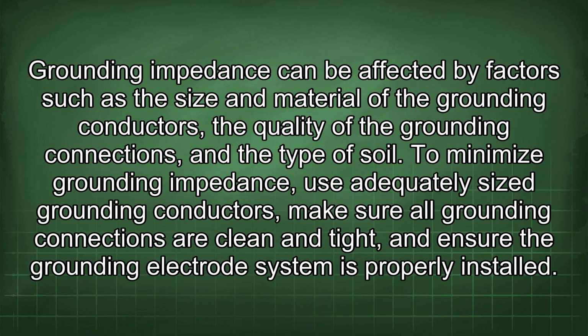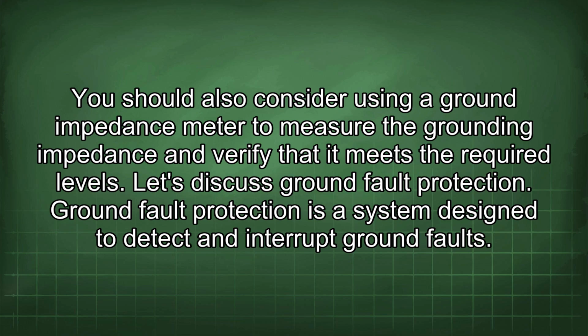Grounding impedance can be affected by factors such as the size and material of the grounding conductors, the quality of the grounding connections, and the type of soil. To minimize grounding impedance, use adequately sized grounding conductors, make sure all grounding connections are clean and tight, and ensure the grounding electrode system is properly installed. You should also consider using a ground impedance meter to measure the grounding impedance and verify that it meets the required levels.